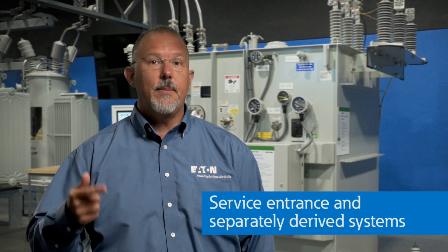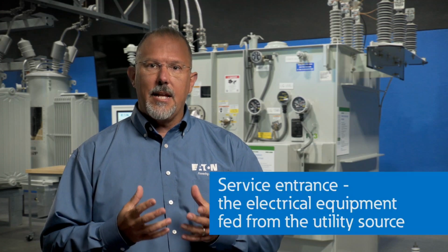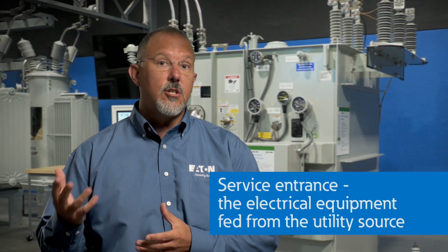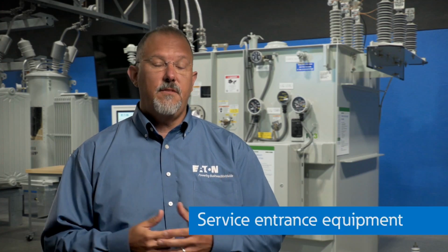For a larger electrical system, we have to consider many other things to properly ground and bond this electrical system. We will give a few examples of components and systems to hopefully clarify any confusion that may arise. Let's talk about 2 important terms, service entrance and separately derived systems. Simply put, think of service entrance as the electrical equipment fed from the utility source. This may include a transformer, a service disconnect, or other protective devices. There are very specific rules in the National Electrical Code for service entrance equipment and grounding.